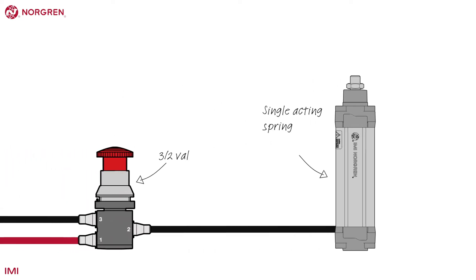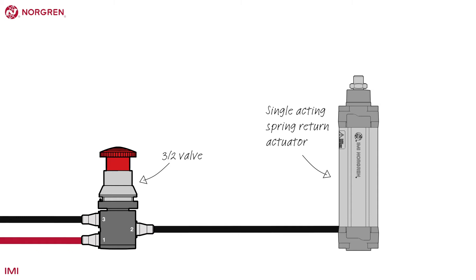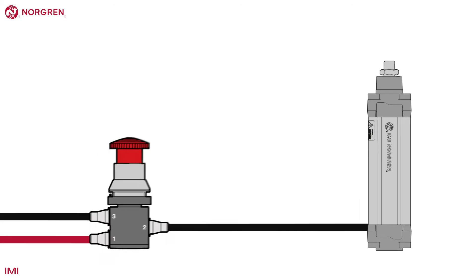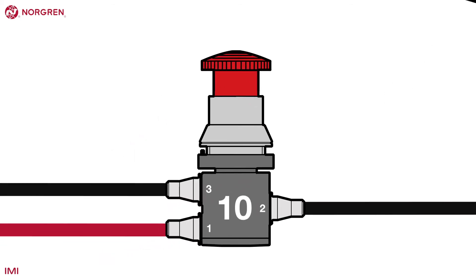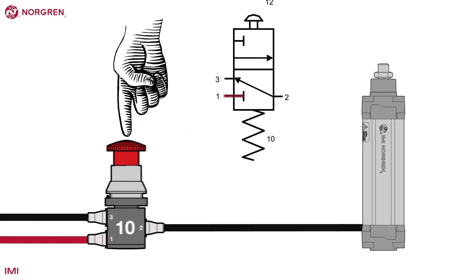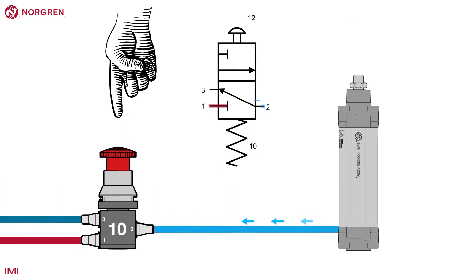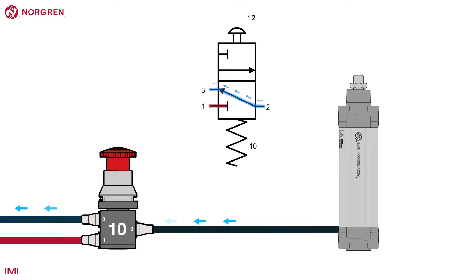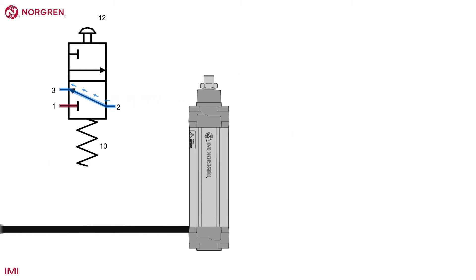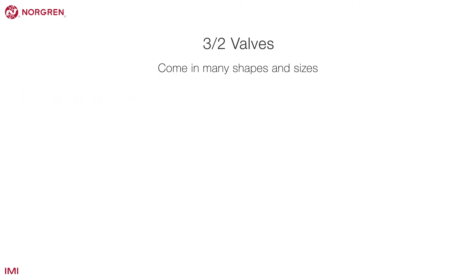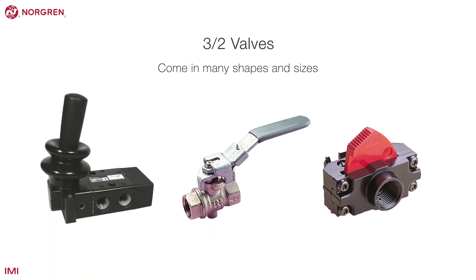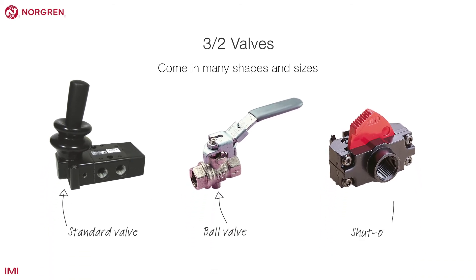Here is a simple example of a 3-2 valve operating a single acting spring return actuator. Initially the system is at rest, the button is not pressed and the valve is in the 1-0 position, so no air is passing to the cylinder. When the button is pressed, the valve moves into the 1-2 position and air passes through the valve to the cylinder. When the button is released, the valve moves back into the 1-0 position and the air between port 2 and the cylinder vents through the exhaust port. 3-2 valves come in many shapes and sizes, but the principle is always the same, whether it's a standard valve, a ball valve or a shut-off valve.